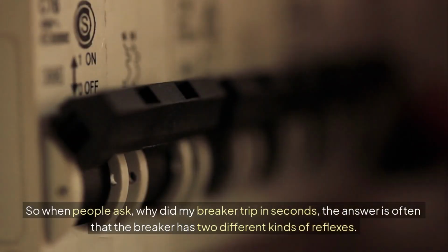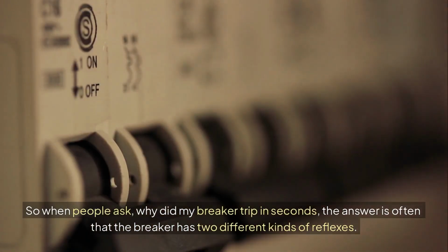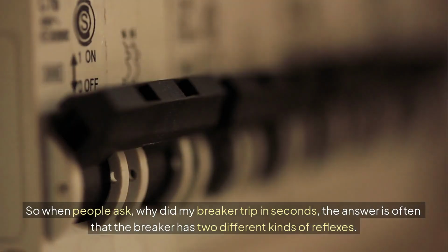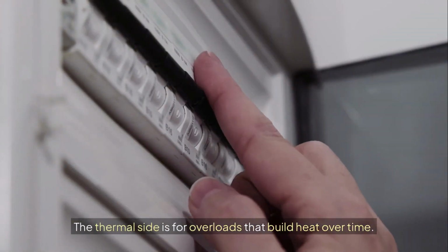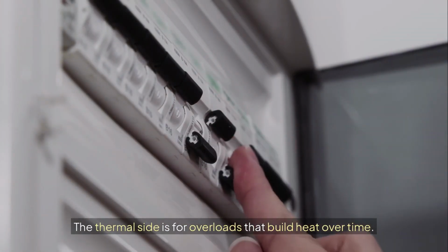So when people ask, why did my breaker trip in seconds? The answer is often that the breaker has two different kinds of reflexes. The thermal side is for overloads that build heat over time.